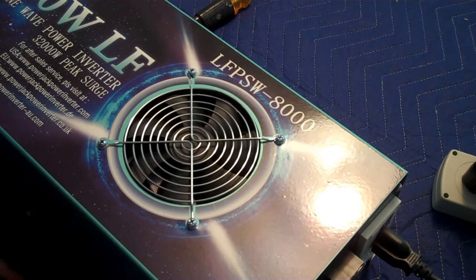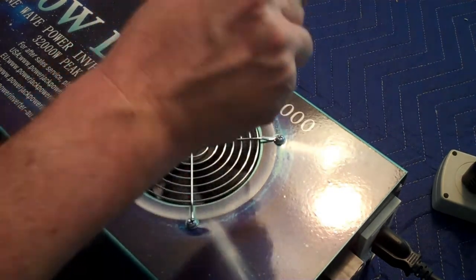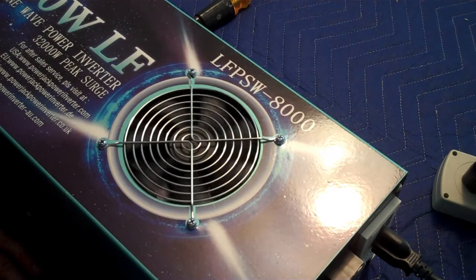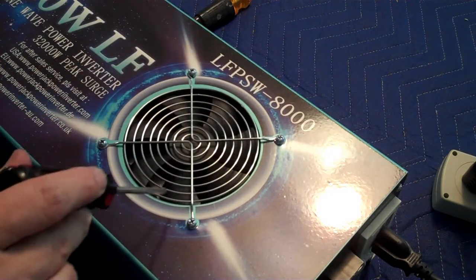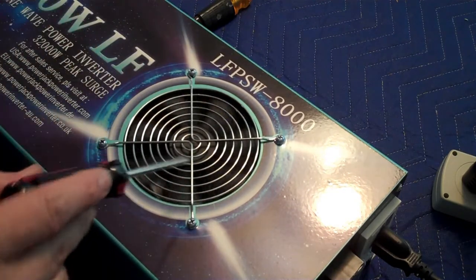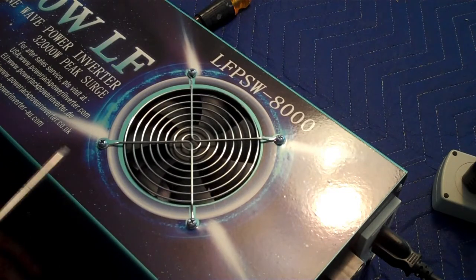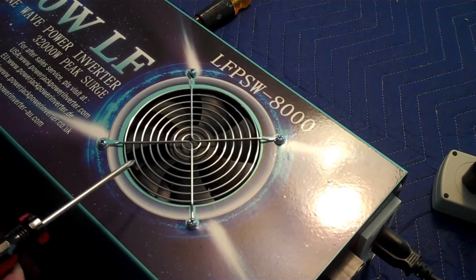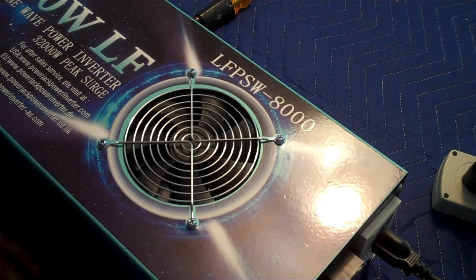All right, after you get the cover back on, take a little screwdriver and make sure this fan can spin freely. When I received it from the factory, that was not the case. There were some wires stuck up in there, and if the temperature sensor on the transformer had tried to turn on the fan, it would have been stuck. So at least now, if the transformer temperature sensor gets high enough to turn on this fan, it can turn on.